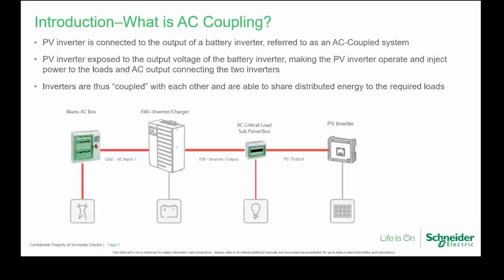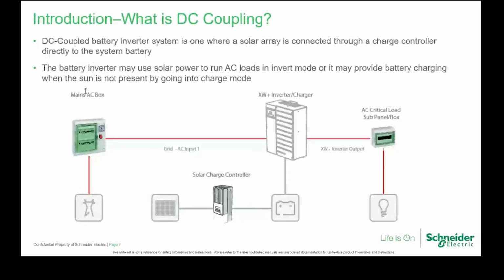On DC coupling, basically you'll have a solar charge controller rather than the PV inverter. In this case, the solar charge controller charges the batteries. Then the batteries provide the power to the XW Plus inverter. And that will again go back to the loads, or back to the grid if you're allowed to export.